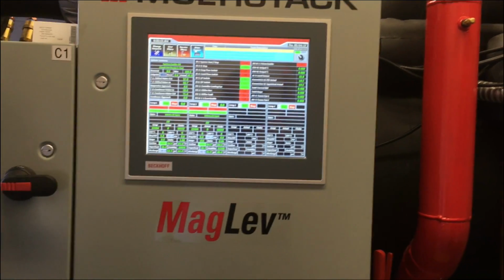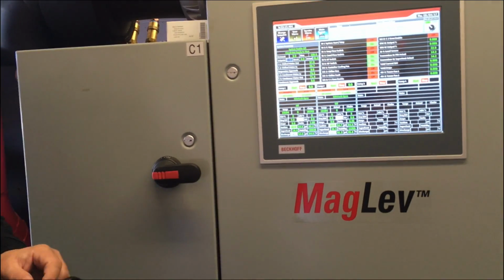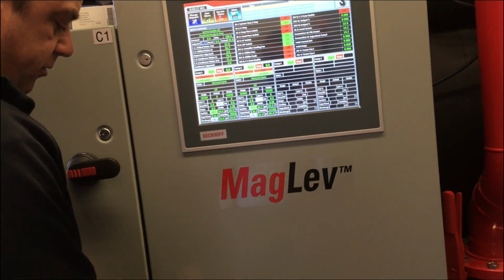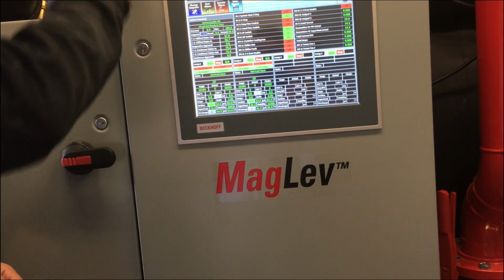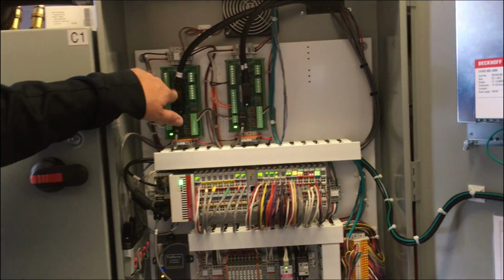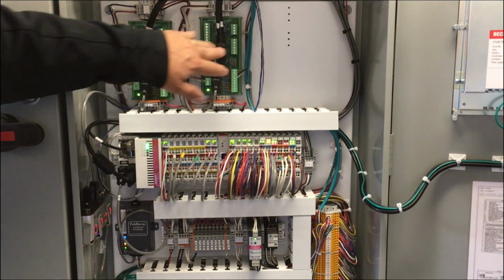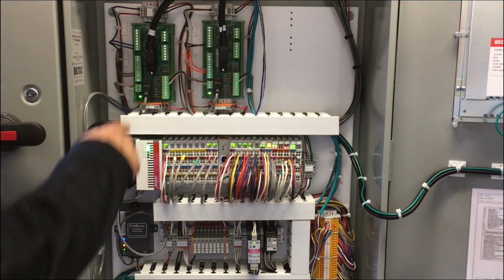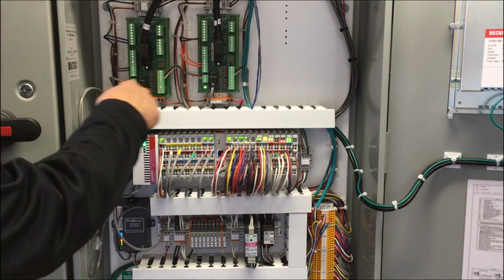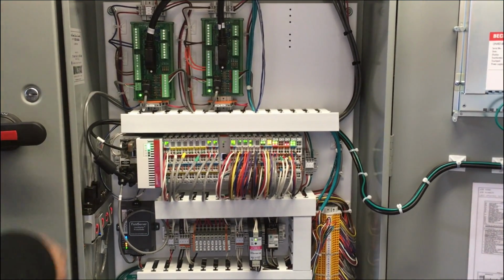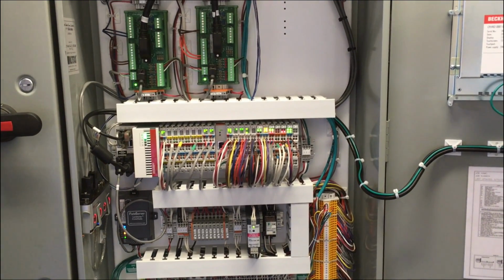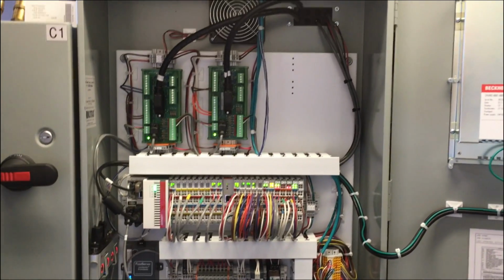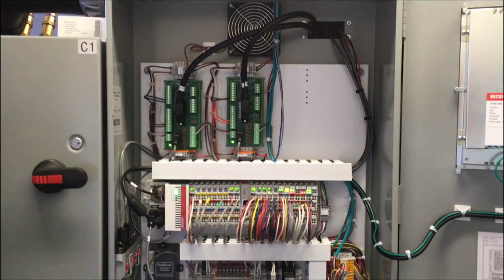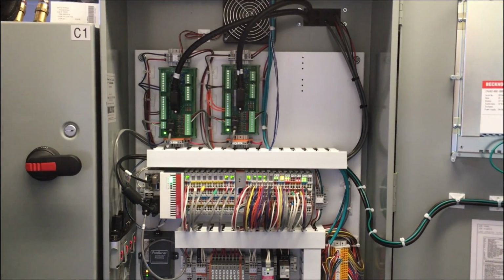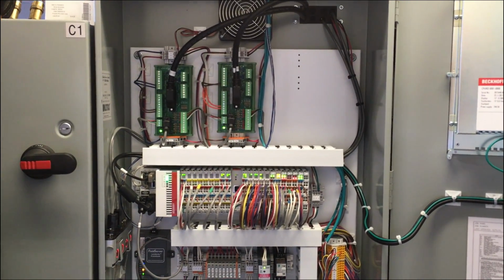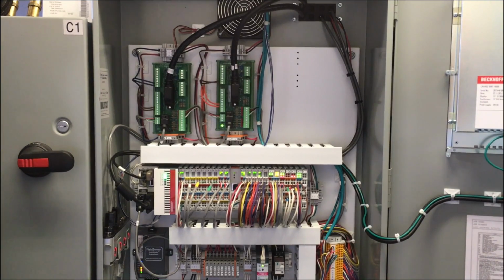There's a board inside here. There's a direct link to the compressor. It's actually part of the compressor. So this board right here is called the compressor in-out board, I/O board. It's got a little green light on it right here. That light is the capacitor bleed for that compressor. When that light goes out, it takes about 1.5 minutes. I just blindly tell people shut off for 5 minutes and don't cheat, and then come back on and you'll be all set. It should go out. Yeah, it's out.